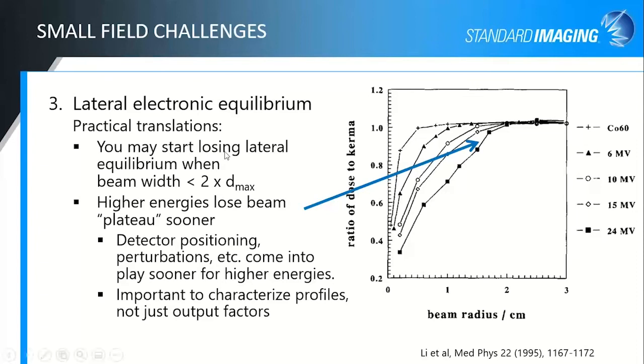And generally then, because of that condition of being less than twice your Dmax, your higher energy beams are going to lose this flat plateau, the flat center of the field, or flat-ish if you're talking FFF, sooner than the lower energies will. So you actually hit small field conditions earlier on a higher energy beam as you're going down in field size than you do with a lower energy beam. So your detector positioning is critical. That issue comes into play sooner for those higher energies. It also means that it's important to characterize the profiles of your beams and to understand how that changes for your machine, not just measuring the output factors at the center.